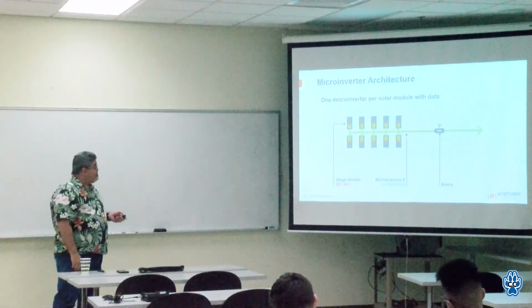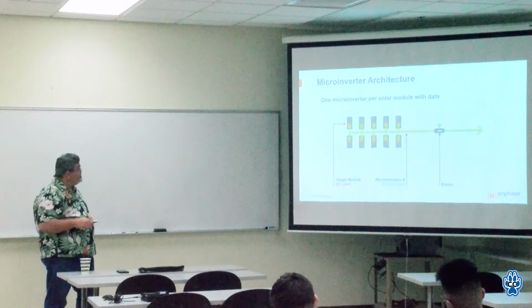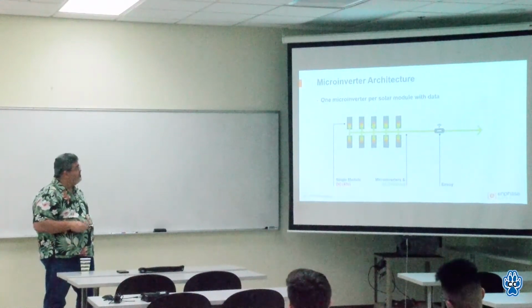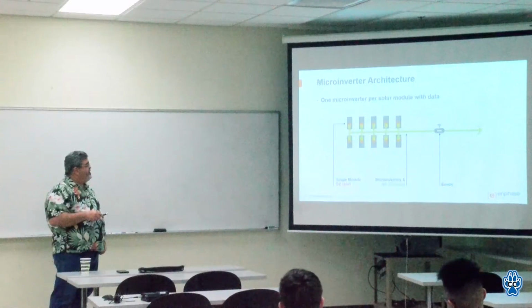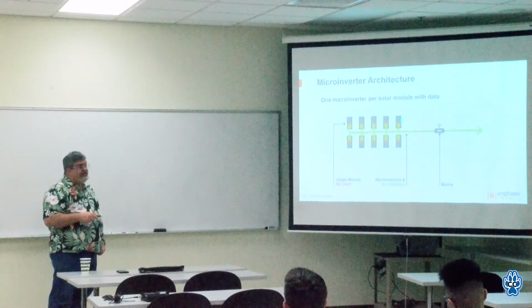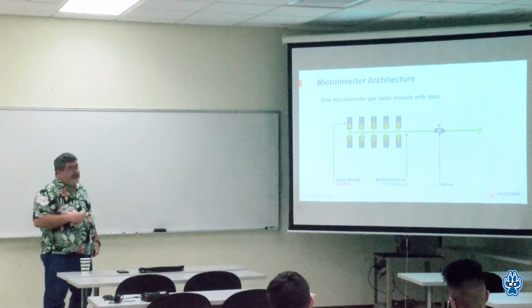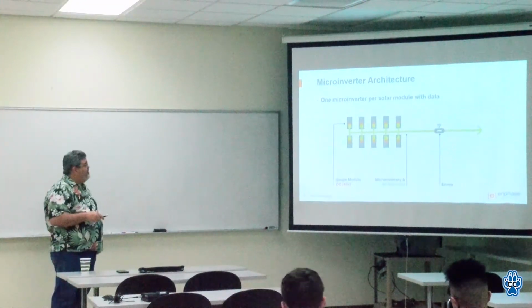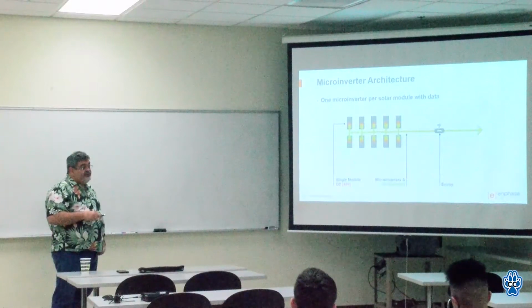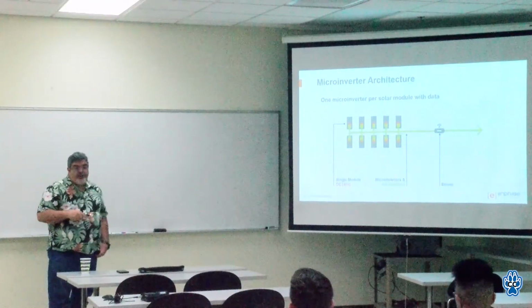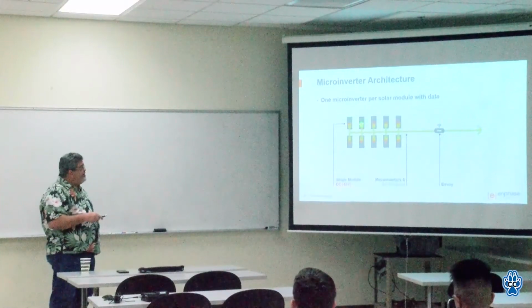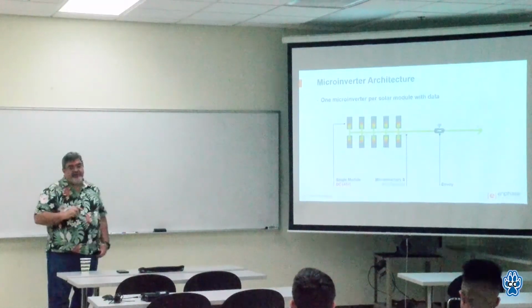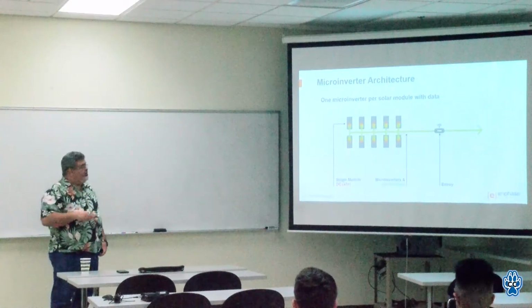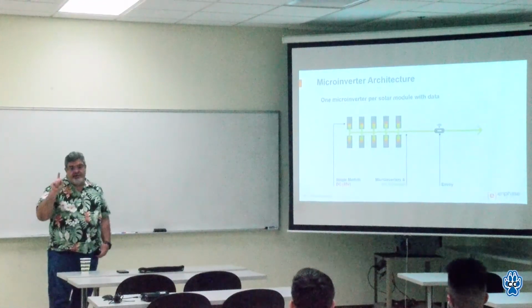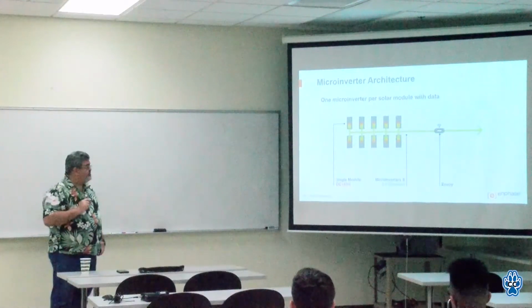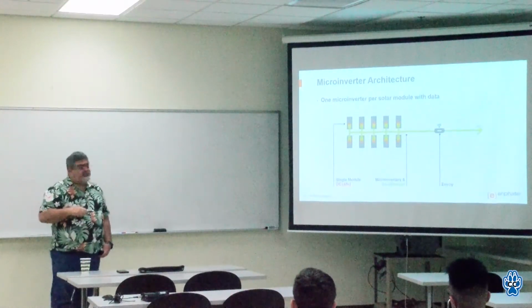Each one of the modules here has a microinverter attached to it, and all of these are now connected not in series but in parallel. So here, if I have shadow on one of these, it will put out less power, less current. But all the rest, which could be in full sunlight, are still putting out their maximum current. So if one of these is shaded, you've only lost the output of that one module. It doesn't affect the whole string.